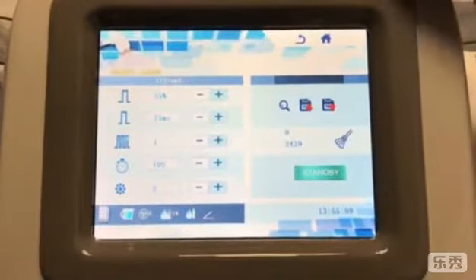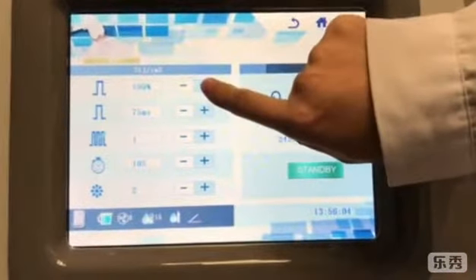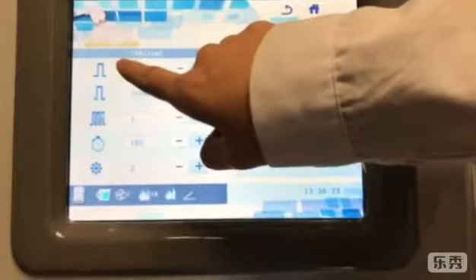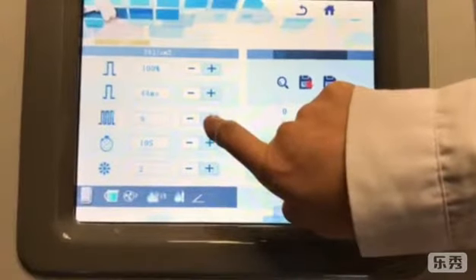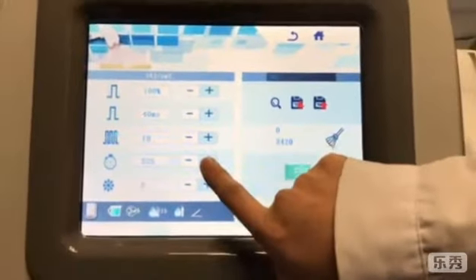But in case there is a problem, you can check this window first to see which part is broken — to save cost and save time for your customers. From here you can see our energy. The highest energy can reach 166 joules. Frequency from 1 to 10 hertz, treatment time from 10 seconds to 30 seconds.